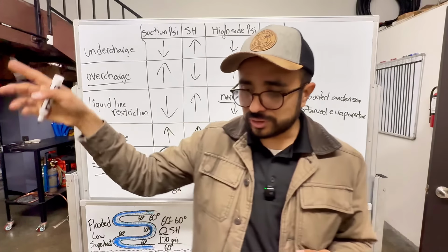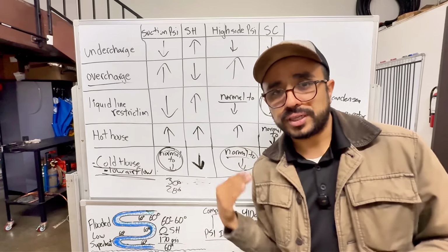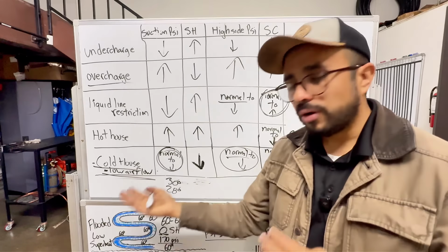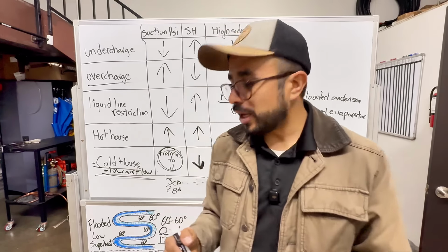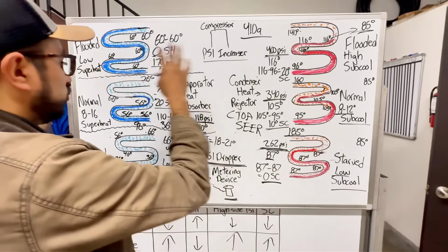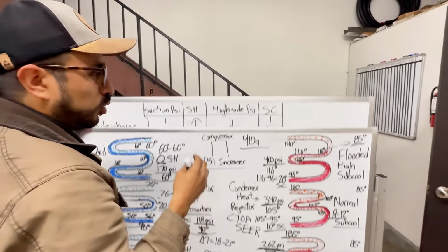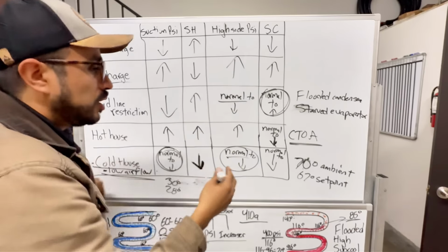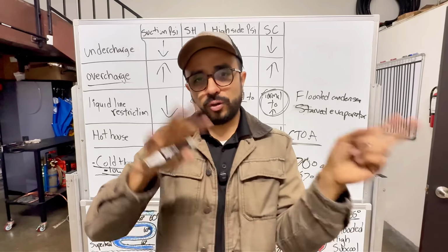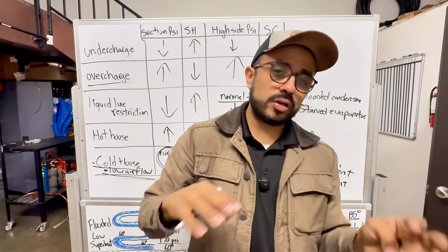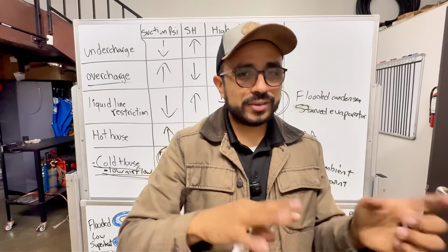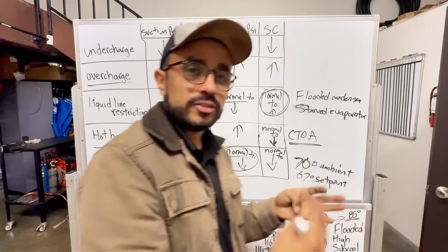Trying to think of other ones if you're working on a system that has a piston. And there are great HVAC troubleshooting charts online that you can check out. But I just thought to briefly go over what happens with subcool and superheat, and how when you go to a job, and this is where you want to get to, you can connect your gauges, of course, airflow before charge, check that airflow is good, no dirty filter, condensing coil is clean, wait 10-15 minutes, and then check your pressure, superheat and subcool.